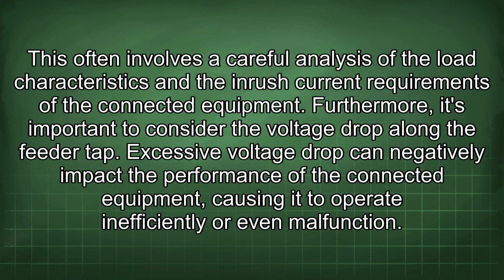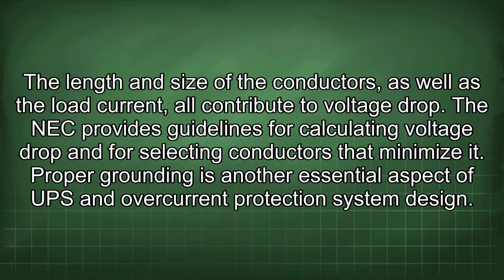Furthermore, it's important to consider the voltage drop along the feeder tap. Excessive voltage drop can negatively impact the performance of the connected equipment, causing it to operate inefficiently or even malfunction. The length and size of the conductors, as well as the load current, all contribute to voltage drop. The NEC provides guidelines for calculating voltage drop and for selecting conductors that minimize it.